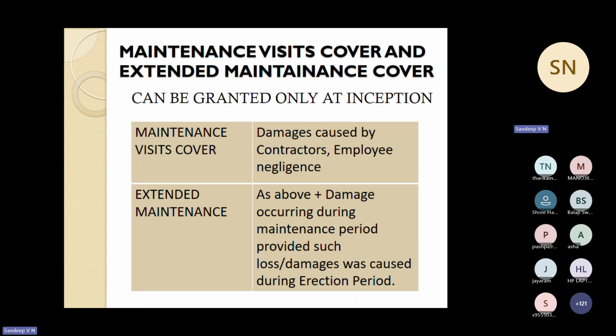Now the root cause analysis found that there were 4 bolts fixing the pump set to the foundation. Only 3 were tightened. So during the erection period, the employees who did the erection - contractor's employees, subcontractor's employees, or even the principal himself doing the erection - there was negligence, an erection fault. The 4th bolt was not tightened, but the machine was commissioned with this defect unnoticed.